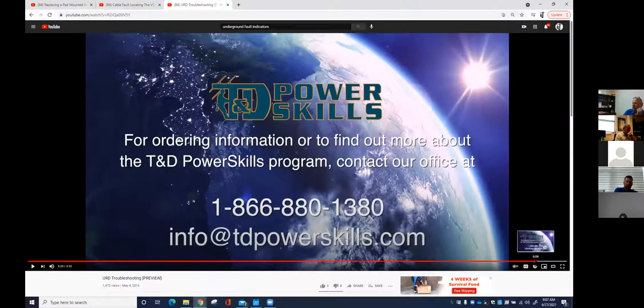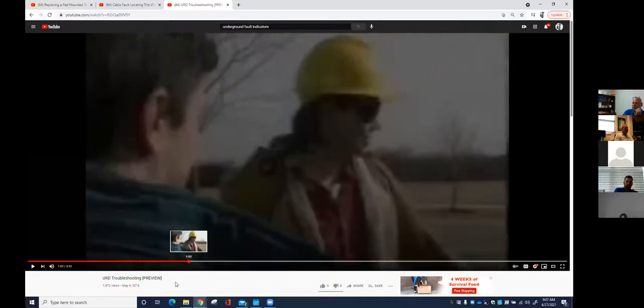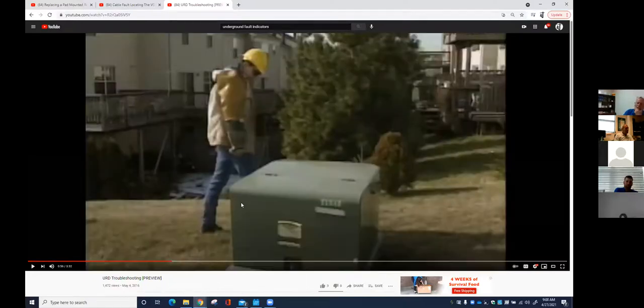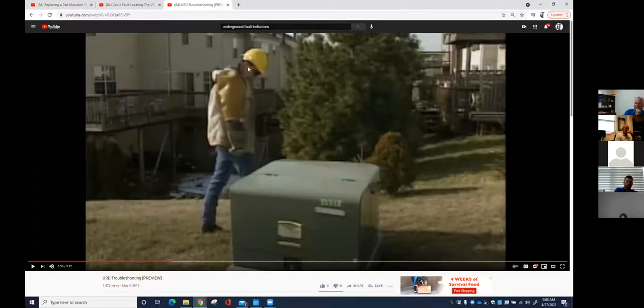What I want to touch on first, guys, is the gentleman that's doing the work here. He's got on all his PPE correctly. He even has on the sleeves, rubber gloves, hard hat, safety glasses. I don't think this is the correct hard hat that a lineman's going to wear — you're going to have the one with the full brim that's rated for an arc — but anyway, he's got his PPE on and he's doing his thing.